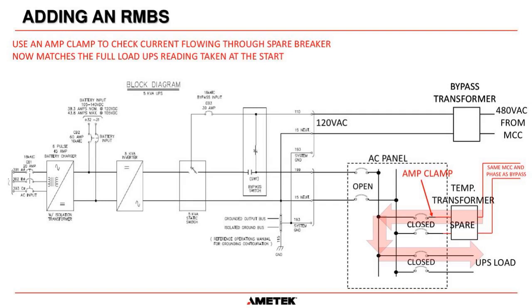How do we do the maintenance for the PCB control inside the RMBS? Very good question again. I will have to get back to you on that. In truth, I would assume we would go to the isolated bypass position, and that would allow us to replace that PCB. I would have to check the drawings and be absolutely clear that that PCB is then going to be volt-free, but I'm pretty sure that is the case. The isolated bypass would remove power from the PCB. Actually, maybe it doesn't. Maybe there's a lamp that's still lit when we're in the isolated bypass position. I will get back to you on that one. Very, very good question. But I promise I will get back to you on that.